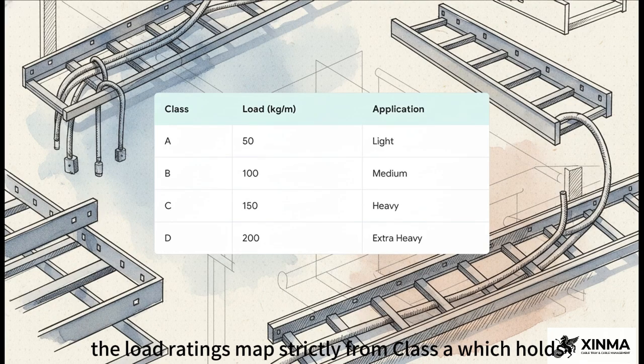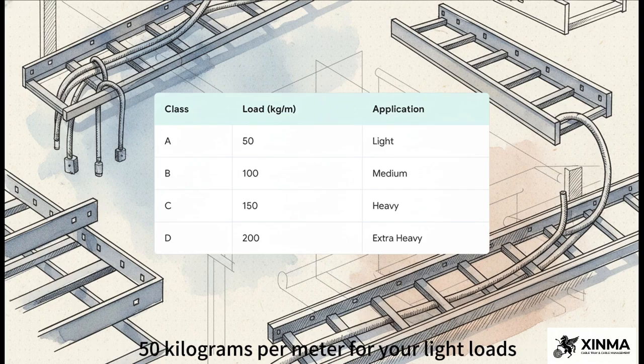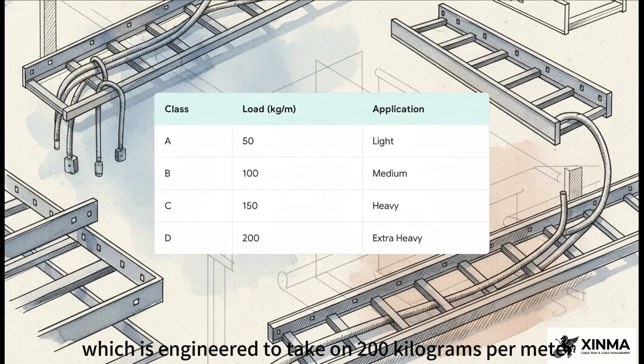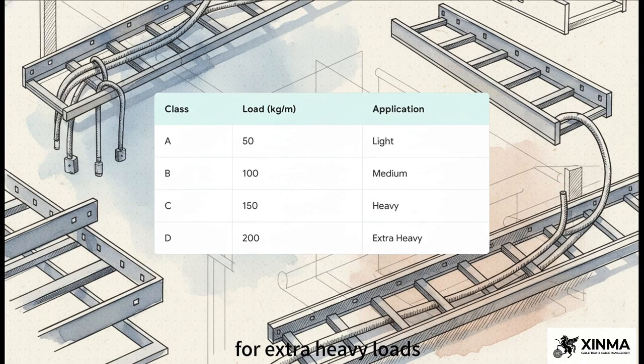The load ratings map strictly from Class A, which holds 50 kilograms per meter for light loads, stepping up all the way to Class D, which is engineered to take on 200 kilograms per meter for extra heavy loads. You simply cannot guess here. You absolutely have to match the class exactly to your actual installation conditions, making sure you account for every single heavy power cable that will rest on those rungs.